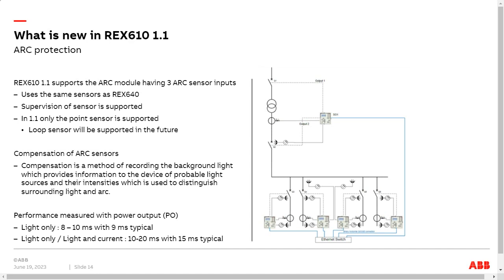Then, as REX610 only has normal power outputs, we can see these performance times there. With light only, 9 milliseconds typical, and then there's another row with light and current. So if you want to use the current function in this arc protection, then it's 15 milliseconds typical. Of course, we could improve these times quite significantly by having high-speed outputs, but we have other products with those high-speed outputs if those are desired.